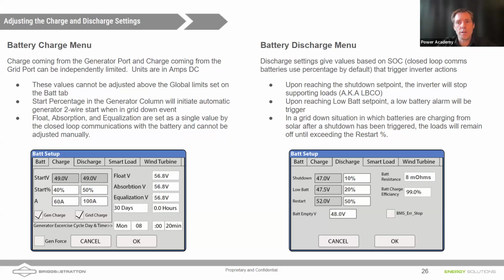Once we do initiate a generator charge cycle, it will finish that cycle, bringing the battery up to a 95% state of charge. Now, we can use time of use to limit that so that we're not charging with a generator when we don't want to. And we'll talk about that. One comment: we only really have to set the hour time here to 0 in order to prevent the generator exercise cycle from taking place. Also note that the float, absorb, and equalization are all set to the same values here.